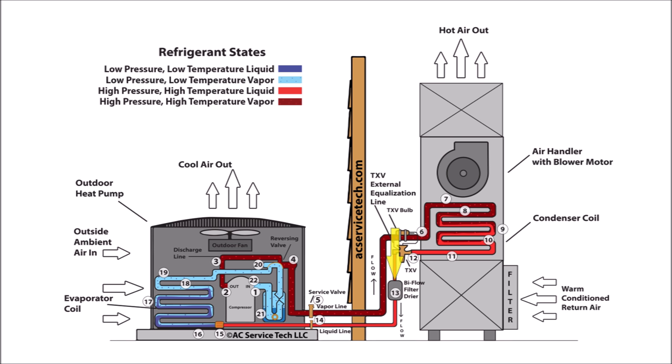At step thirteen, the subcooled liquid goes through the bi-flow filter dryer where the dryer traps any debris and any water. The filter dryer has a fixed capacity due to its size. After the refrigerant flows through the filter dryer, it remains a subcooled liquid refrigerant. Step fourteen is where you have the high pressure, high temperature, subcooled liquid refrigerant flowing through the liquid line service valve. Over at step fifteen, you have the high pressure, high temperature, subcooled liquid refrigerant entering the metering device, and then you have a low pressure, low temperature liquid on the other side.